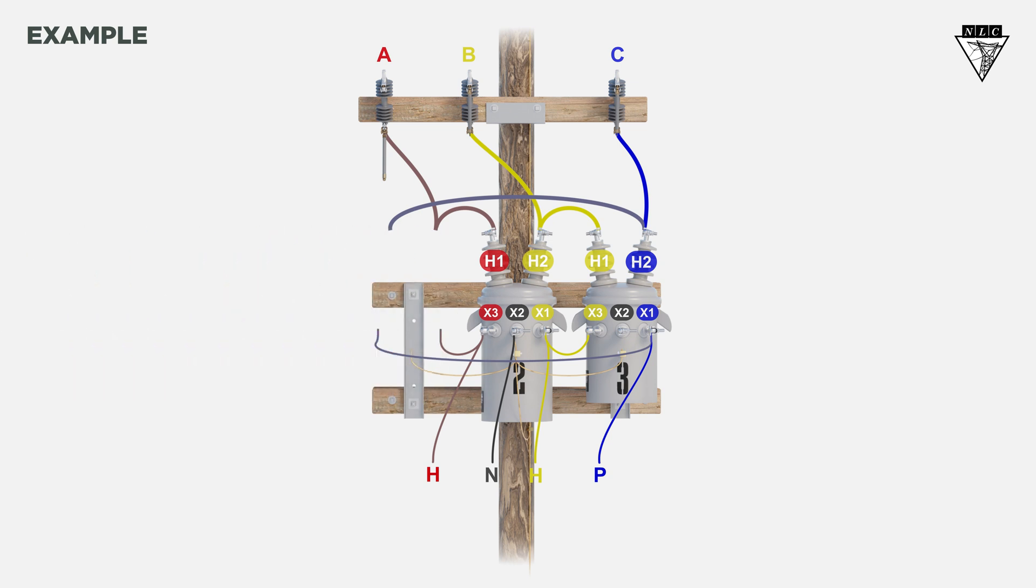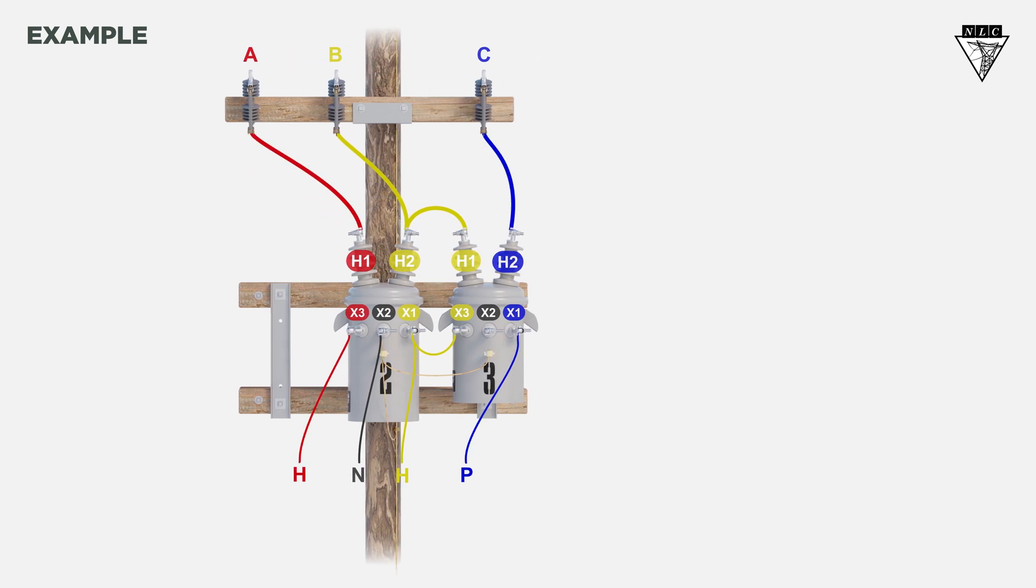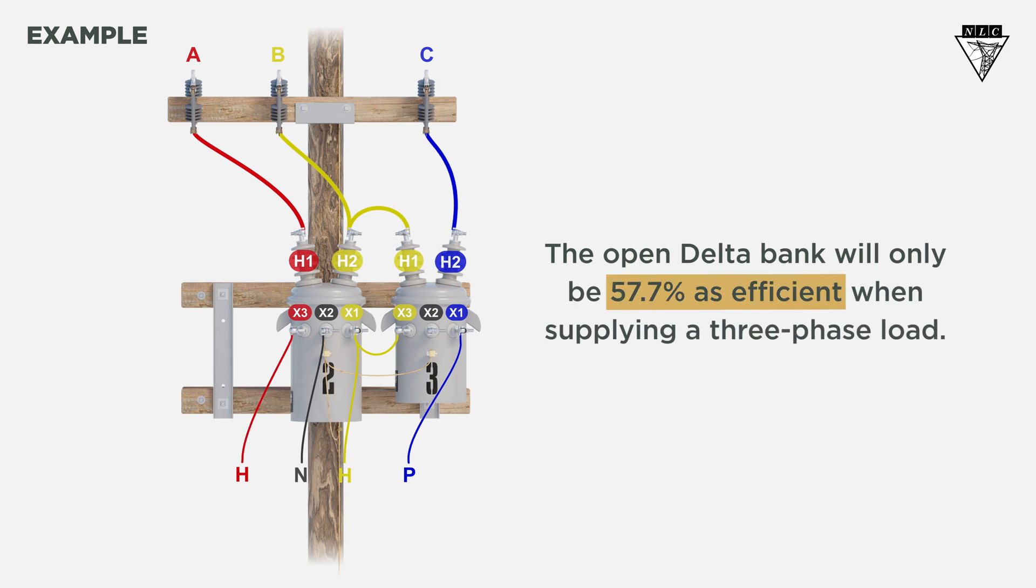However, the customer requests that the power be returned immediately. In this scenario, you can reconnect the delta delta bank as an open delta connection and continue to run power to the customer. However, the open delta bank will only be 57.7 percent as efficient when supplying a three-phase load, so it's best used temporarily.